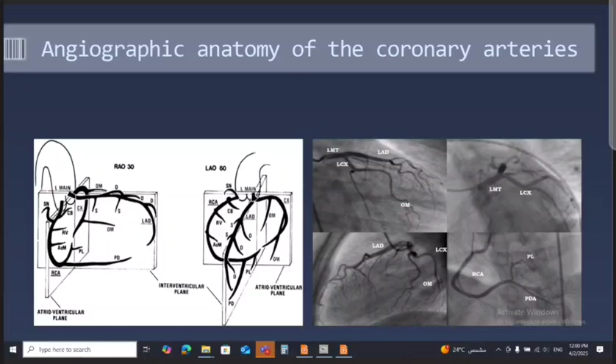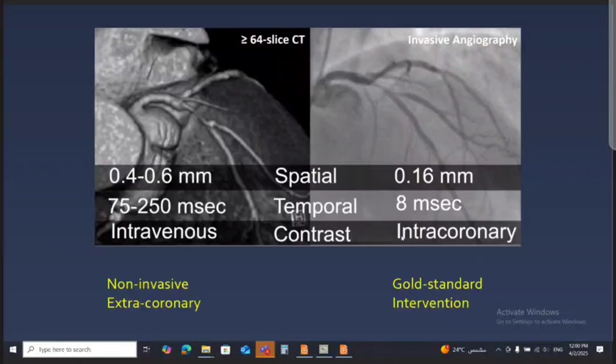Because in the catheter we inject intracoronary, while in the CT we inject intravenous. And so definitely the concentration of contrast will be much, much better in conventional angiography than CT. This is the slide. The spatial resolution in the CT is lower than the spatial resolution of angiography. Temporal resolution of the CT at its best is 75, while the temporal resolution of angiography was 8 milliseconds. The contrast resolution in the catheter is much better because we inject intracoronary, while in the CT we inject intravenously.